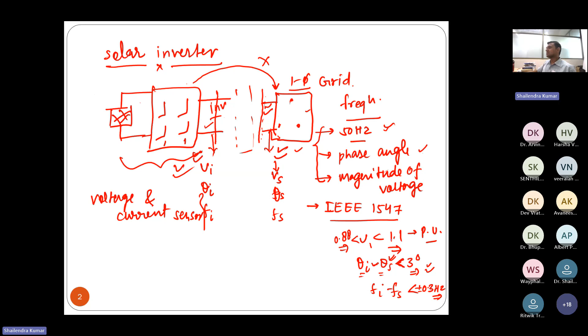Yes, magnitude we can get. We can sense the voltage at the converter output side, and we can sense the parameter at the grid side -- both sides we can sense. And we can take the difference, then we can get the magnitude -- what is the actual magnitude, whether it is between 0.88 and 1.1 per unit, or going beyond this limit. If it goes beyond this limit, you are not able to synchronize your converter with the grid, so it will operate in standalone mode, right? So all these three conditions must be satisfied: the magnitude must be within this limit, theta must be within this limit, and frequency must be within this limit.